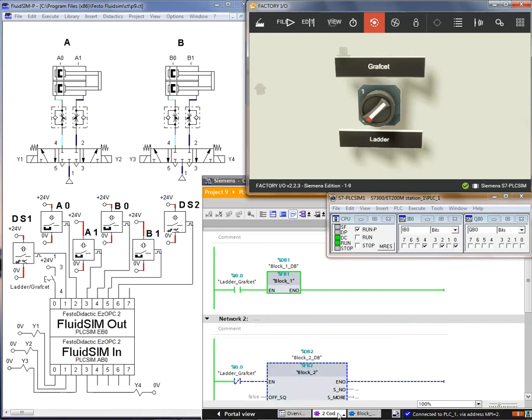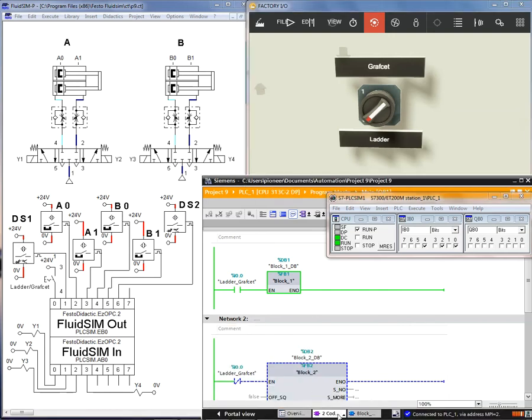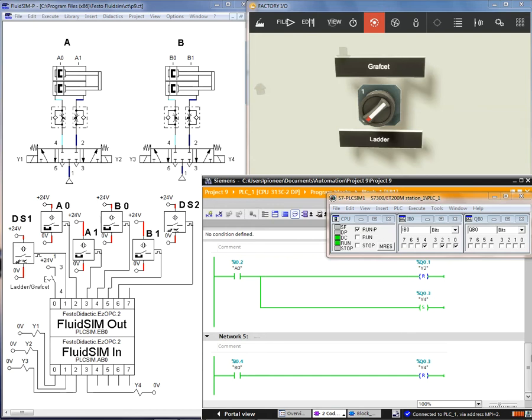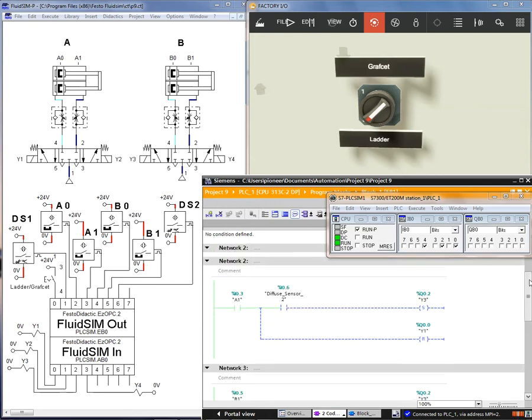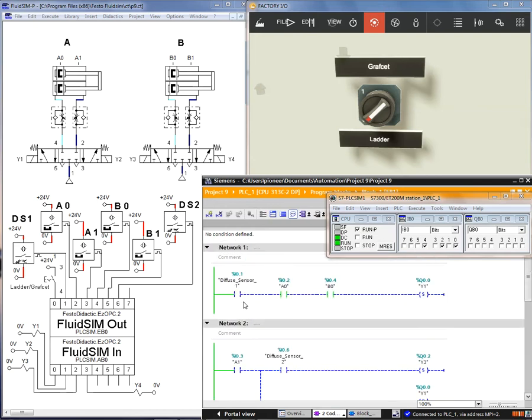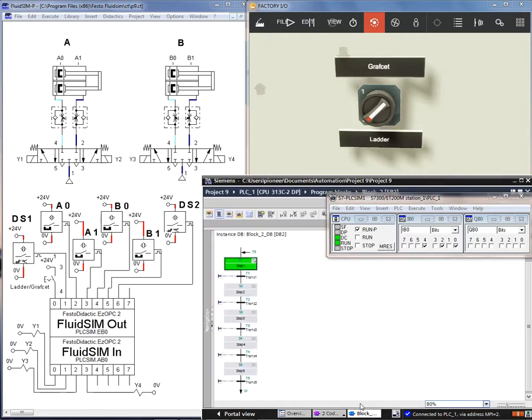Let's see FB1 — Function Block 1. You can see the ladder programming language. I will describe it in this simulation. And FB2, or Function Block 2: you can see five steps from S1 going to S5. This is a jump command — it means after S5 it goes back to step 1. You can see the transitions and the steps.